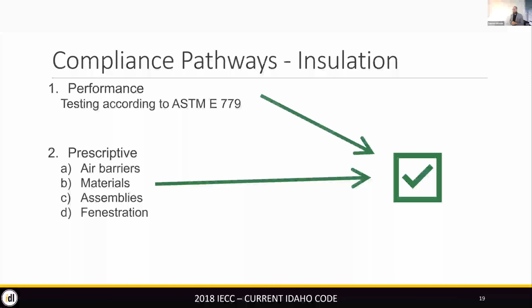The performance pathway involves testing on the structure itself—pressurizing a part of the building and measuring the air leakage. There's a standard out there for doing that. I don't see this occurring nearly as frequently in commercial buildings as in residential buildings, partly because the equipment is larger and more expensive. But home energy ratings and the energy rating index require a blower door test for verification, and for the tax credit, the Energy Star program, those have to be tested.